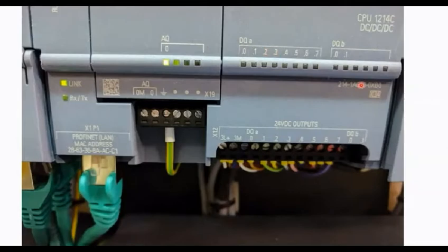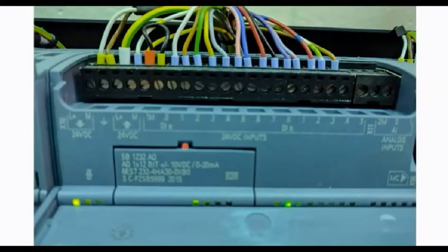And this DQ is the same for the output. For the output, if you are doing sinking. You see this card, I already told you, if you remove this cover you can add one analog output here. So you can easily connect your analog directly, with no need for scaling or anything. That analog is 0 to 20 milliamp, plus minus 10 volt DC. You can add it here.